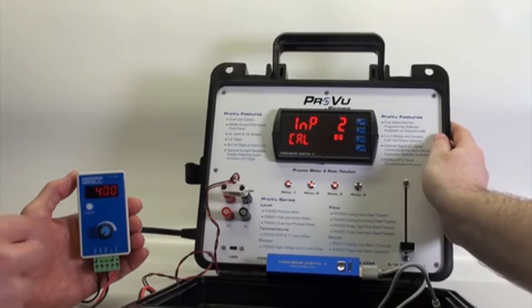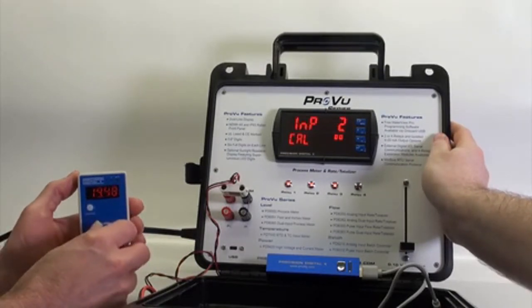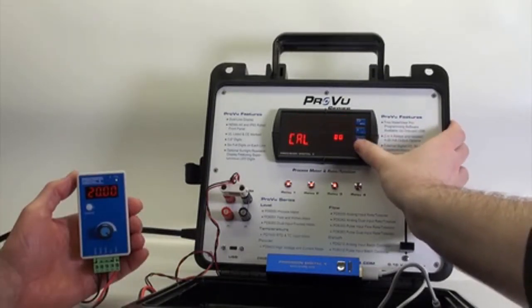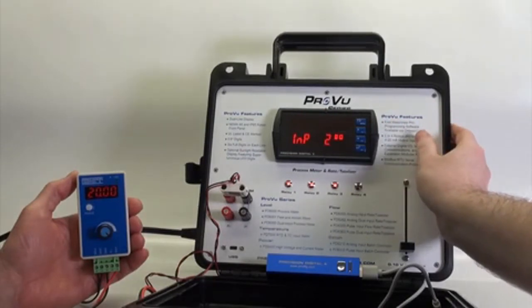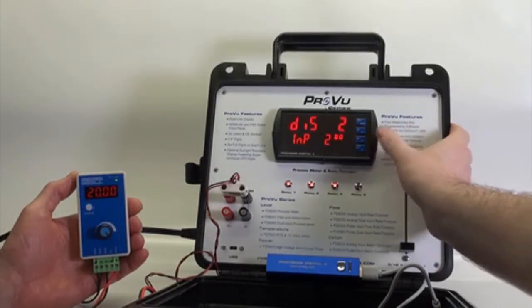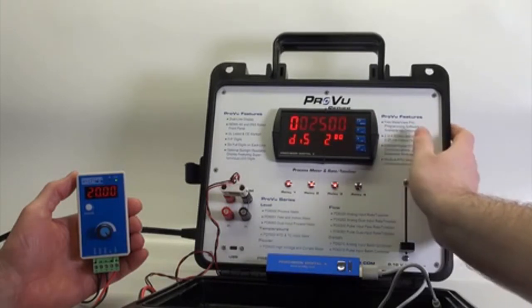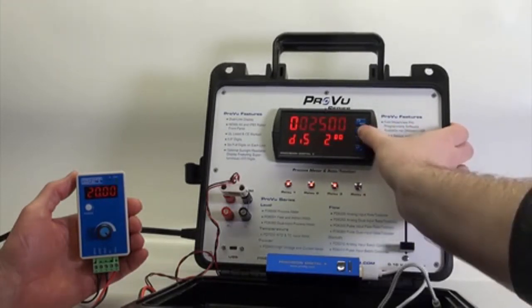And now it's asking us for input 2, so all I have to do is slide the pot all the way to the other side, and we're putting out 20 milliamps. The meter's asking for 20 milliamps, and it reads that input. Now we'll change this to read 5,000.